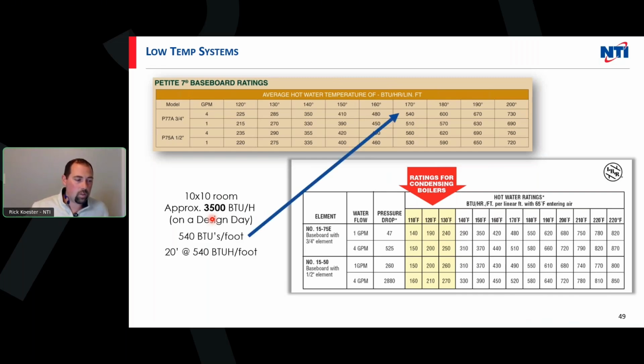And that's exactly what I was getting at, because that's what I use in my example. So if I took 540 BTUs per foot, saying that we're using 180 degrees supply water, 160 return, so an average of 170, I get about 540 BTUs per foot. If I did 20 times 540, I end up giving out 10,800 BTUs for 20 feet of baseboard in a 10 by 10 room that only needs 3,500 BTUs on a design day. And that's the important part. On the coldest day of the year, the design day, I need 3,500. Yet if I did 20 feet of baseboard, which is very common everywhere you go, you end up putting out about 10,800 into the space. And that's how oversized we really are from room to room.